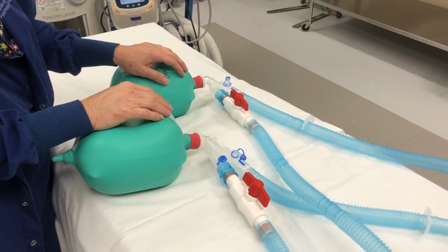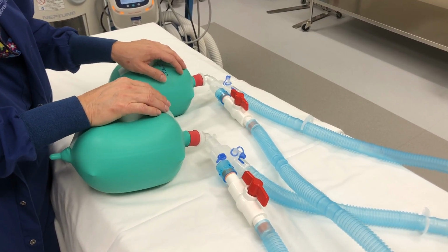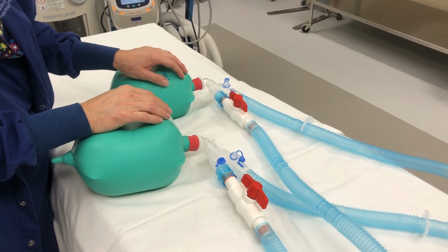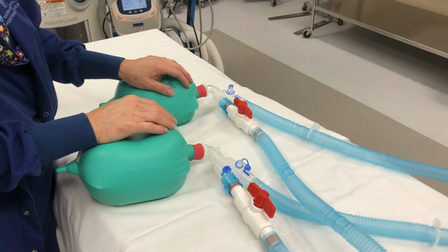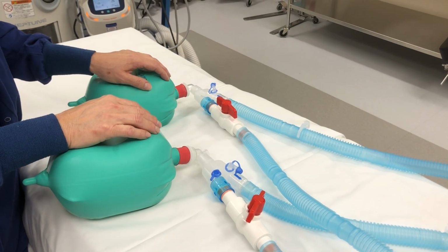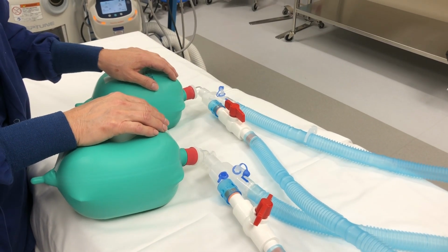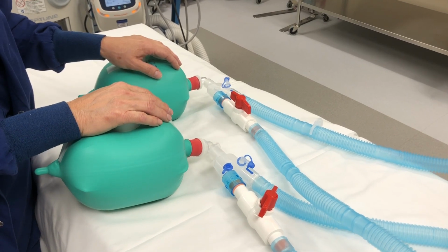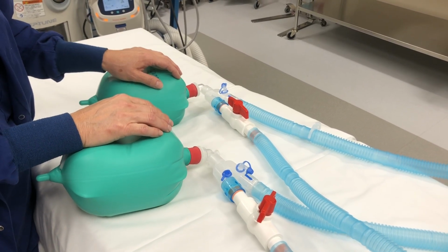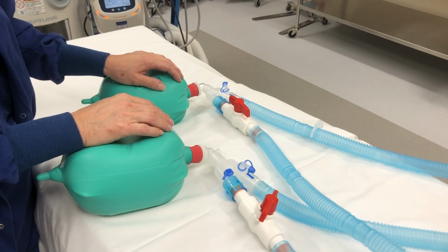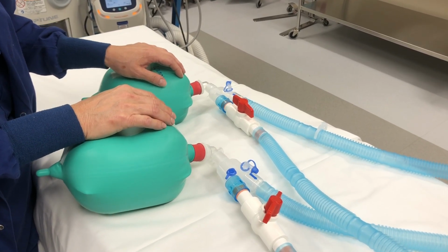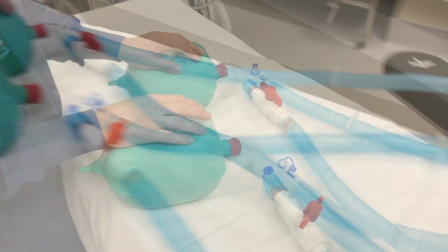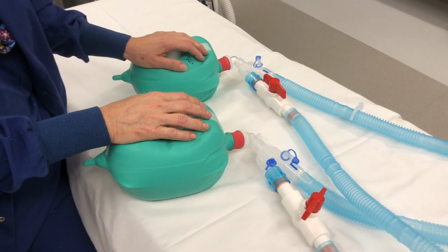So as you can see, I've installed this homemade stopcock system into the inspiratory portion of our vent. As you can see on the other side, there is a one-way valve. This is very important for this system to function. As I partially close off this stopcock, you can see that the lungs are inflating at different rates. So decreasing this flow also changes the IE ratio on this, what we would call a good lung. The PEEP and peak pressures should be the same depending on what your set IE ratio is and your respiratory rate.